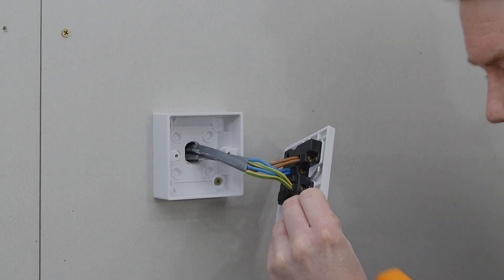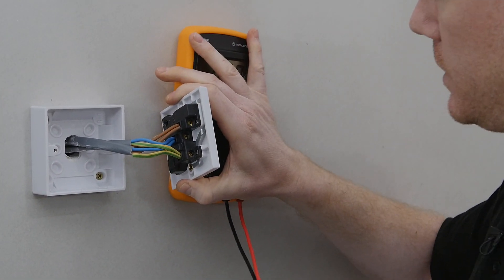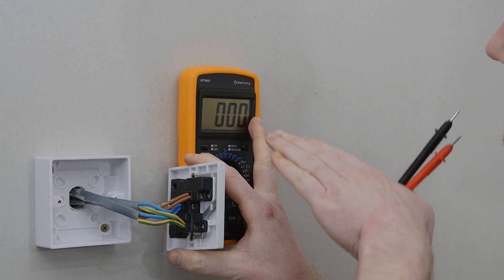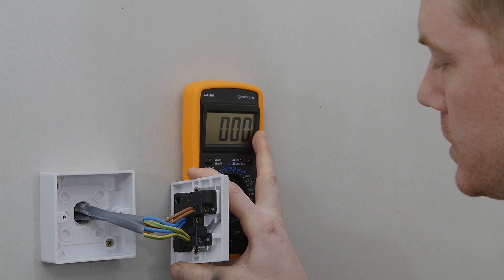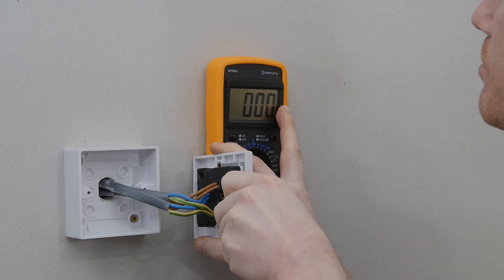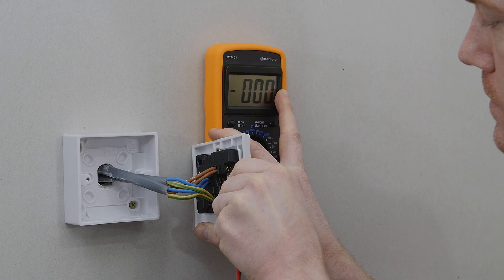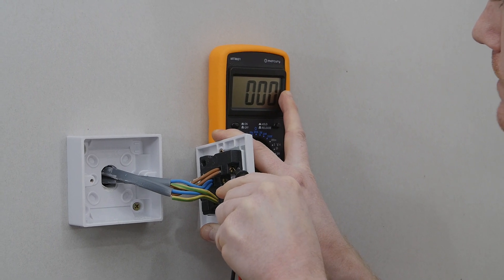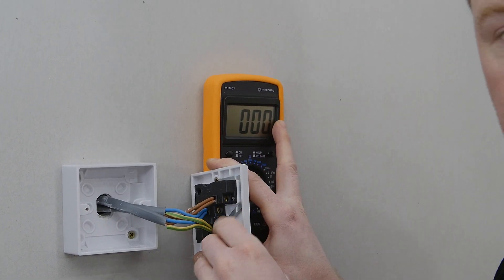What I'm going to do just to ensure that there's no power coming to the socket, I'm going to use a multimeter to test across the connections. So what I've done is set this to the highest AC voltage available. I'm just going to check across the terminals, across all of them using the two probes, and the reading on the meter should not change. So that's one, two, and three. No meter reading change, so I'm free to disconnect the wires from the terminals.